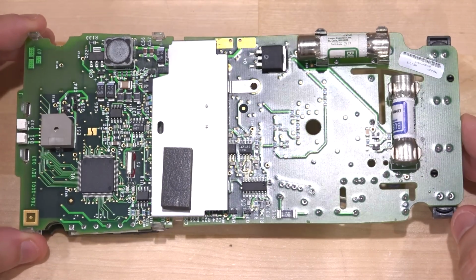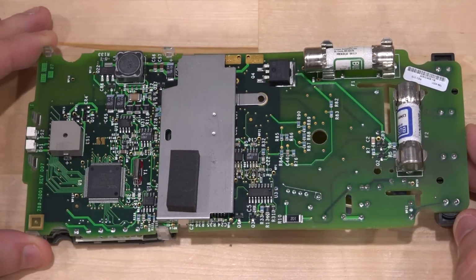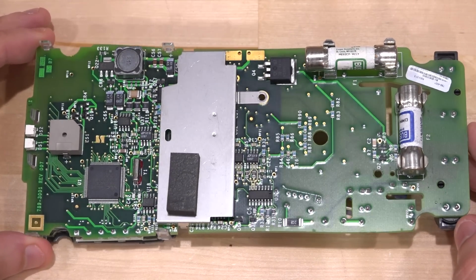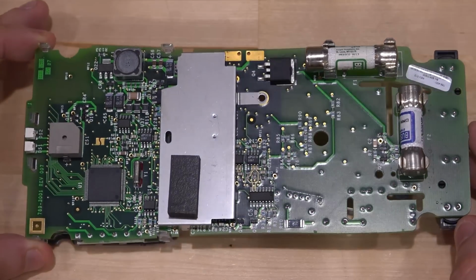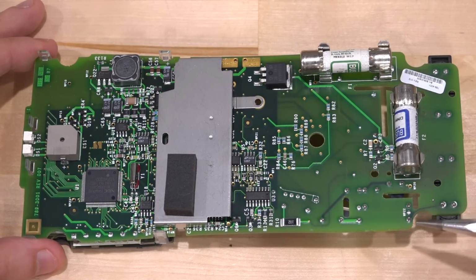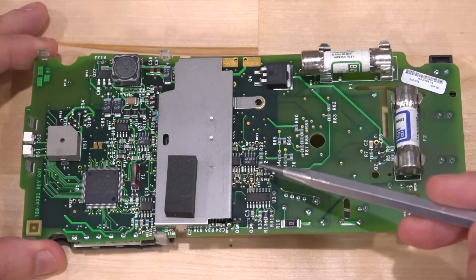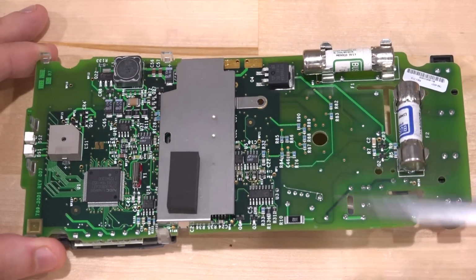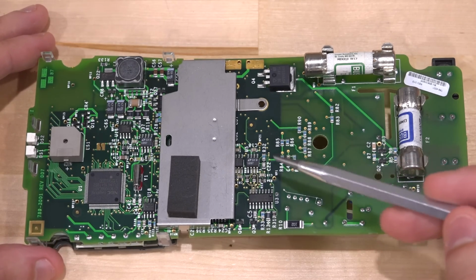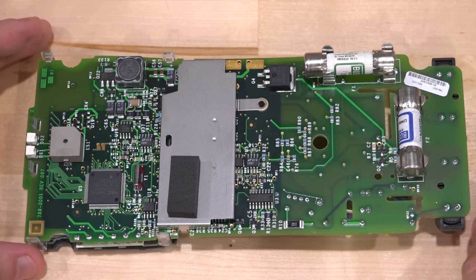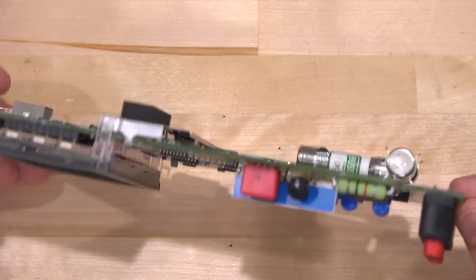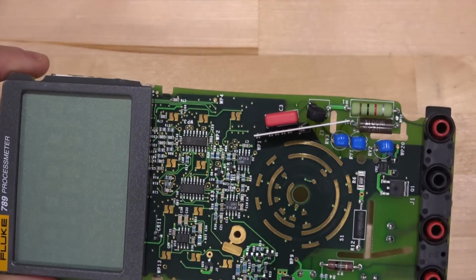The PCB does look a little aged. This is revision 7. So if you have a newer revision, you can share what that looks like on the inside. But it does have a very classic and good design that you would expect from Fluke, appropriate cutouts in the PCB. We do have protected traces over there. You can see they're missing the actual solder mask on top of them, which is what you need for low leakage traces. And on this side, some of the protection circuits are also visible.